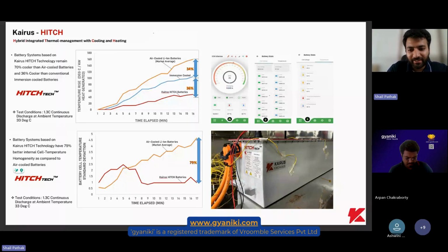As I mentioned, Kairus batteries have a liquid immersion based cooling system. There is a liquid that is thermally conductive yet electrically insulating, and it is circulated inside through a clever flow path. Heat spots are identified by the BMS, and once the temperature through the sensors goes beyond the threshold, the circulation mechanism is actuated. At the casing side, where we get maximum surface area, there are cassettes placed where heat dissipation transfers from internal to external. Did I clear your point, sir?